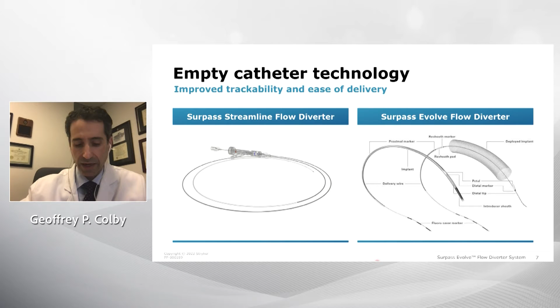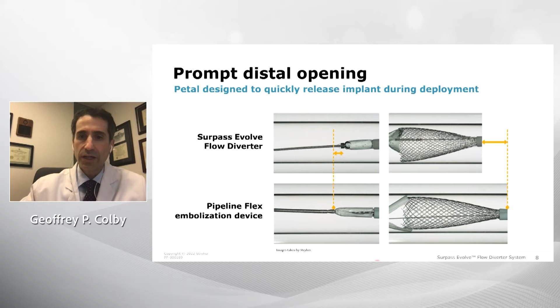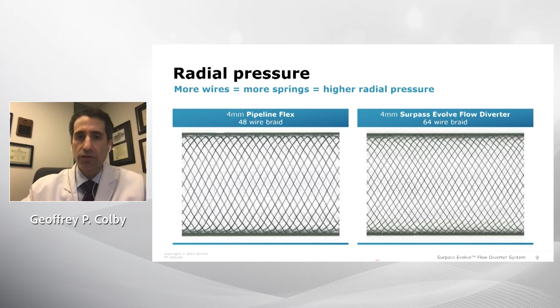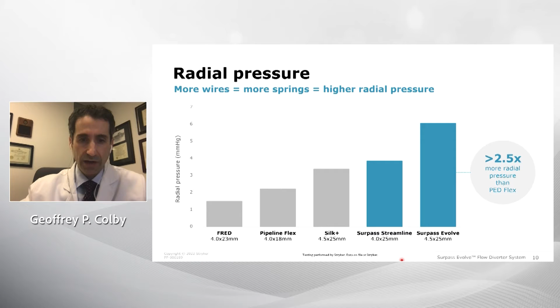You can see Surpass Evolve on the top screen. The petals that constrain the distal end are shorter than some other devices. This allows the device to open up nicely despite the presence of the petals, and you don't need to push as much device out to get that distal end opened. The increased number of wires, so the transition up to the 64 wire braid, has facilitated opening of the device and also facilitates higher radial pressure, which helps with wall apposition. Here's a graph that shows the radial pressure of Surpass Evolve is 2.5 times more than Pipeline, and it's even more than Surpass Streamline, which itself has high radial pressure.